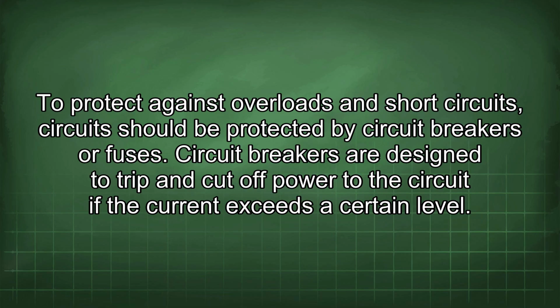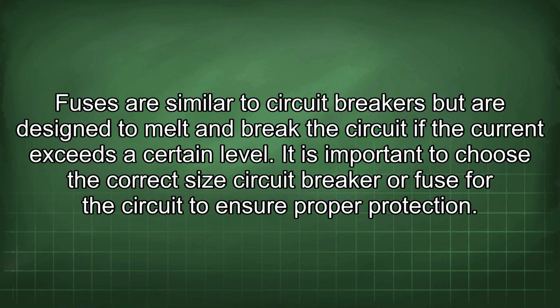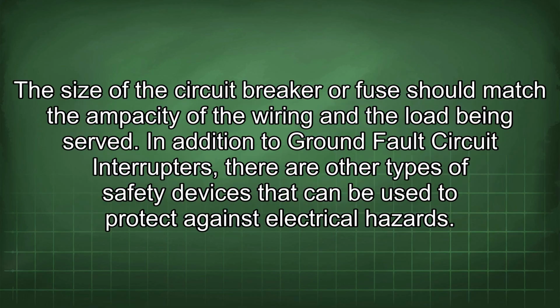To protect against overloads and short circuits, circuits should be protected by circuit breakers or fuses. Circuit breakers are designed to trip and cut off power to the circuit if the current exceeds a certain level. Fuses are similar to circuit breakers, but are designed to melt and break the circuit if the current exceeds a certain level. It is important to choose the correct size circuit breaker or fuse for the circuit to ensure proper protection. The size of the circuit breaker or fuse should match the ampacity of the wiring and the load being served.